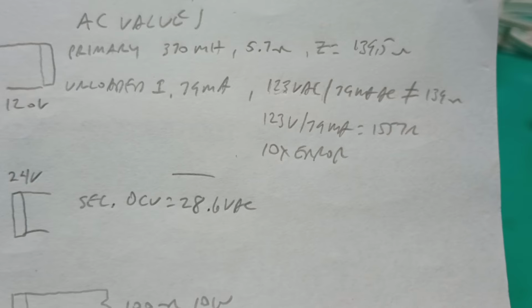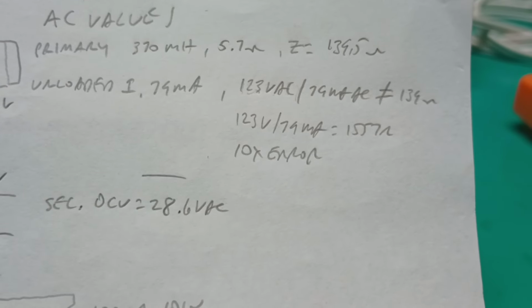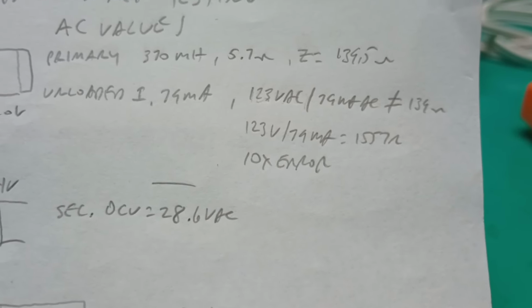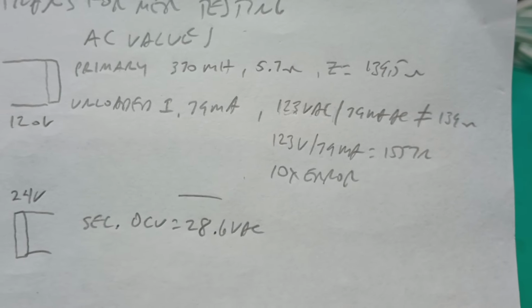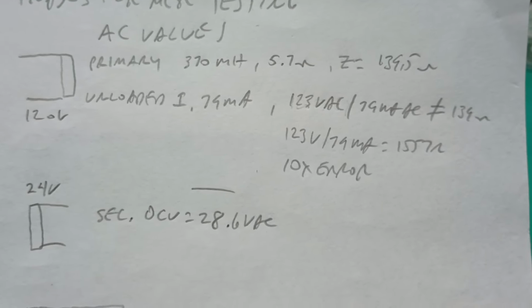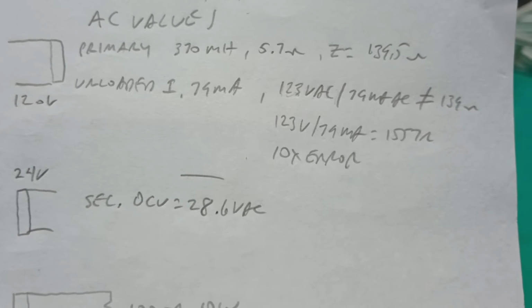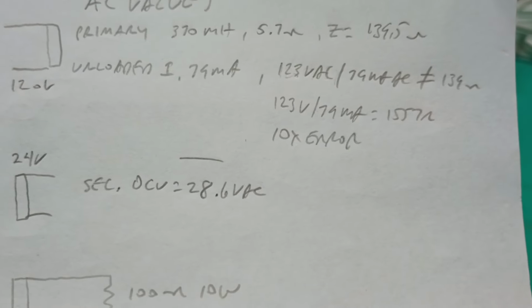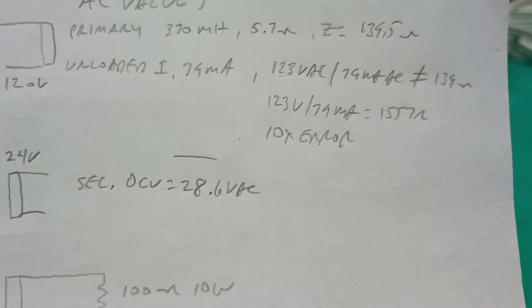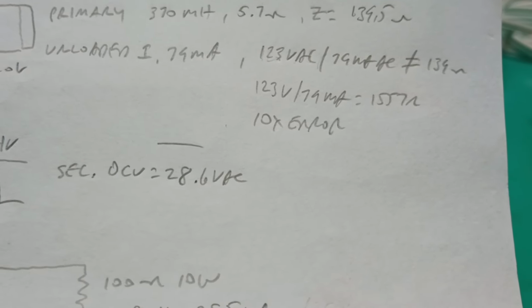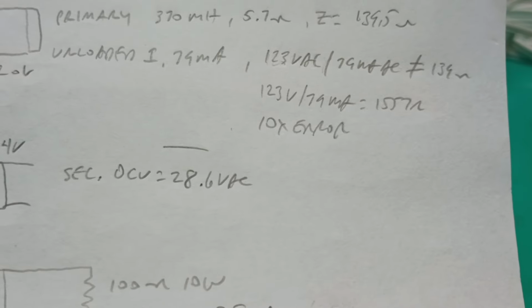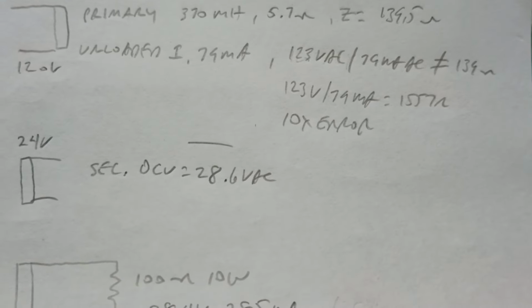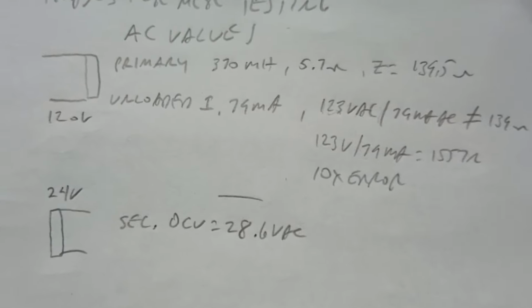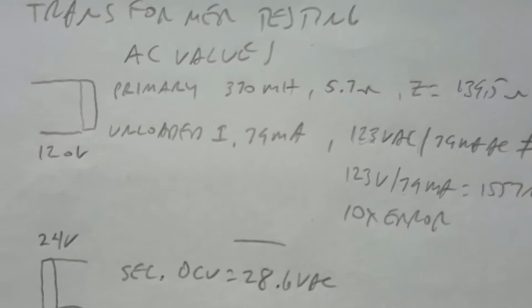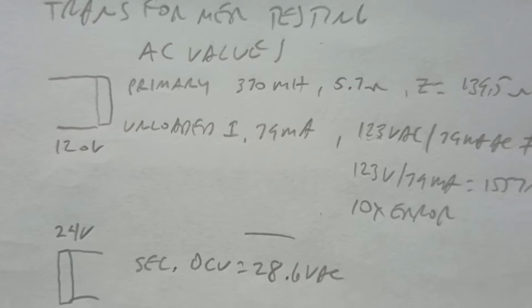123 volts AC divided by 79 milliamp is not anywhere near the impedance of the primary. So we can't use this information to find a primary inductance or impedance, because 123 volts and 79 milliamps, which we know are accurate, means the primary is 1557 ohms, not 139. That's more than a 10 times error. Why? Well, resistance is resistance.